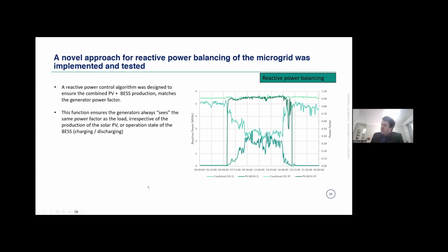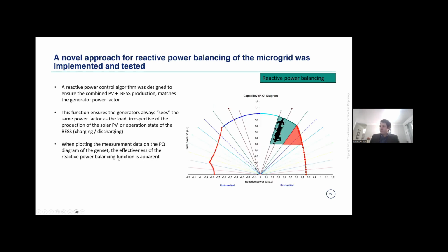And if we look at the graphic here, what we can see is the combined reactive power supplied by the PV and battery essentially matched the power factor of the generators. If you look at the top here, which is exactly what we tried to achieve, which ensured that we always operate our generators within the most efficient point, giving us the best fuel efficiency at any moment in time.